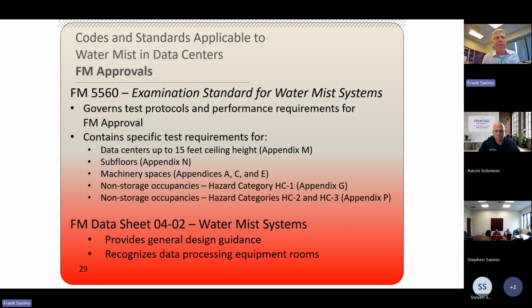For subfloors, Appendix N. For machinery spaces like emergency generators and turbines, it's Appendix A, C, E, and that depends on the volume of that space. That would also apply to, say, an elevator machine room or a utility gas turbine, which would be covered in machinery spaces. Non-storage occupancy, hazard category HC1, which you also know as light hazard, is Appendix G, and then hazard categories HC2 and HC3, which would be ordinary hazard, and extra hazard is in Appendix I. So Appendix P, excuse me. So looking in that standard 5560, you'll see the test criteria and you'll have the definitions for the different hazards that are recognized.